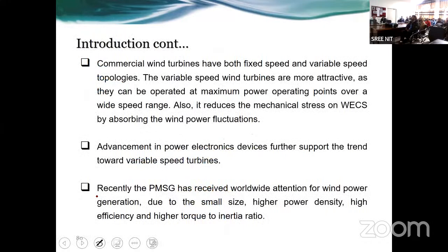So commercial wind turbines have been of fixed speed and variable speed topology. Variable speed wind turbines are more attractive as they can be operated at maximum power operating points over a wide speed range. Also, it reduces the mechanical stress on the wind energy conversion system by absorbing the wind power fluctuations. Advancement in power electronic devices further supports the trend toward variable speed turbines. And recently, the PMSG has received worldwide attention for wind power generation due to its small size, higher power density, high efficiency, and higher torque to inertia ratio.